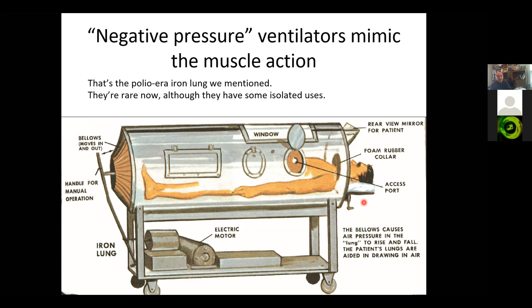So this took away work of breathing, but it doesn't have a way of providing high concentration oxygen other than just some mechanism of spraying oxygen on the patient's face. And it doesn't have a mechanism for providing airway pressures above the difference between atmospheric pressure and the pressure in here as reduced by all the mass of the abdomen and muscles. So on the order of 5 to 10 centimeters of water pressure is the extent of the pressure difference inside to out that could be achieved. In a sick patient, it's not enough. In a COVID-19 patient, it's certainly not enough.